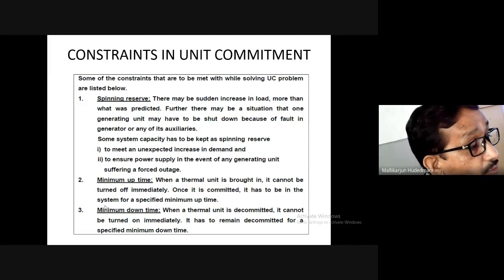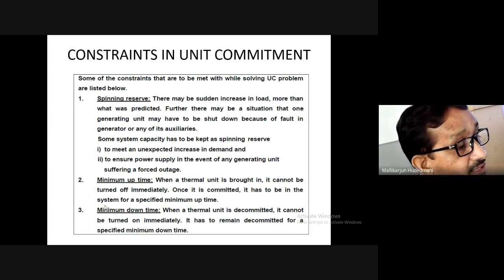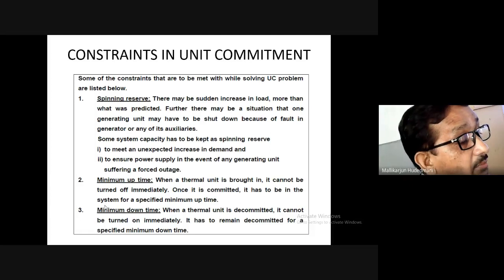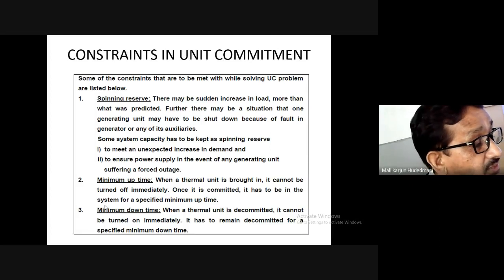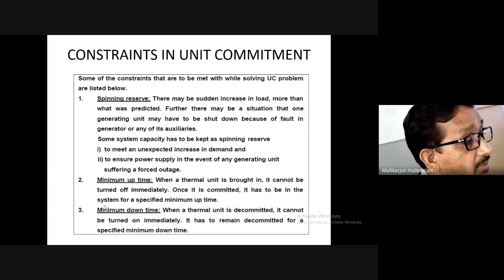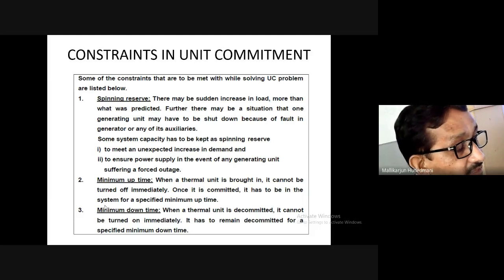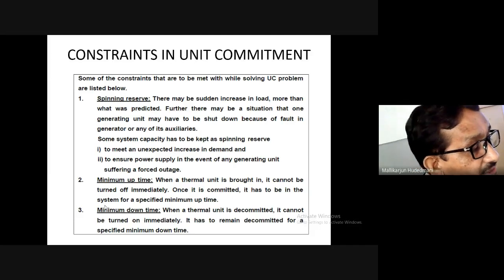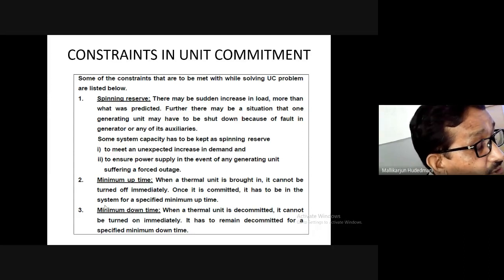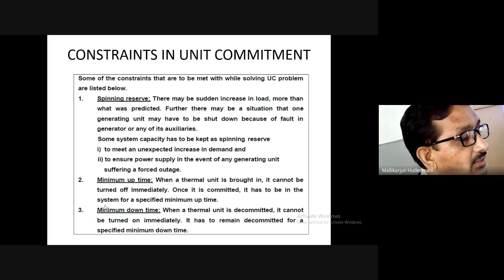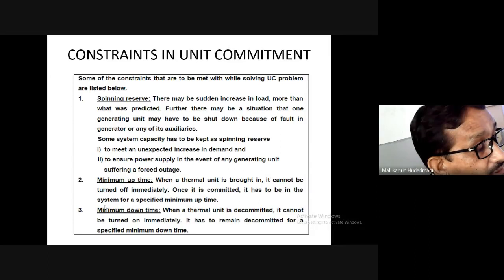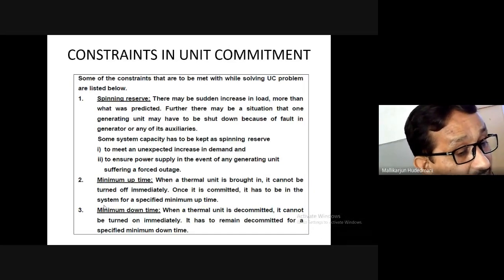Once it is brought to the on state from cold start at room temperature, a particular setup is taken in gradual steps so that it reaches working temperature and is ready to combine operation with the synchronized system. This is minimum uptime - once it is up, after several hours to days I keep it online, generate my required megawatt, and only then schedule when to take it out, because it is not intelligent to run all systems in the plant all the time.